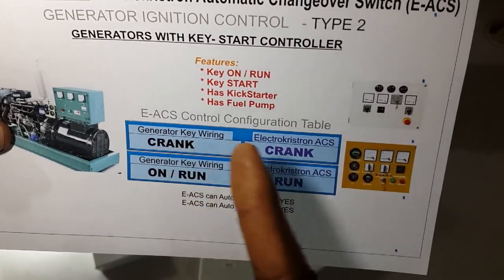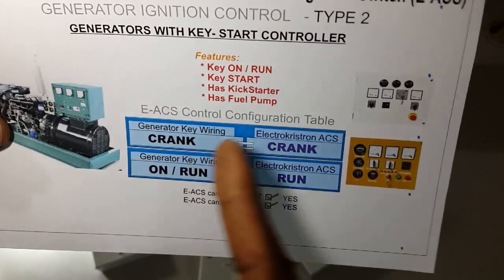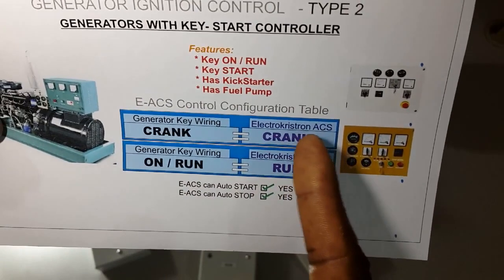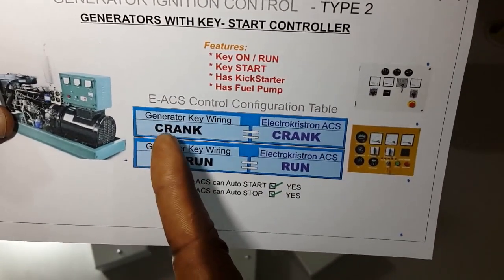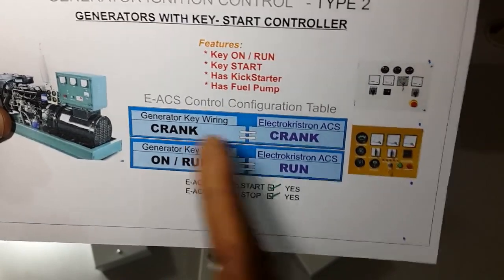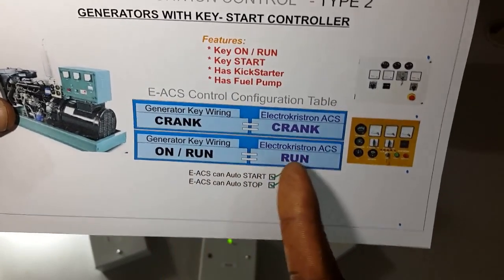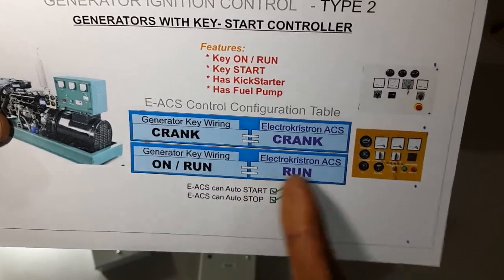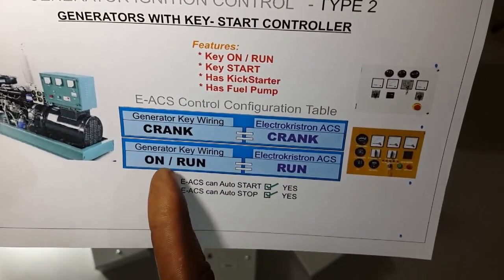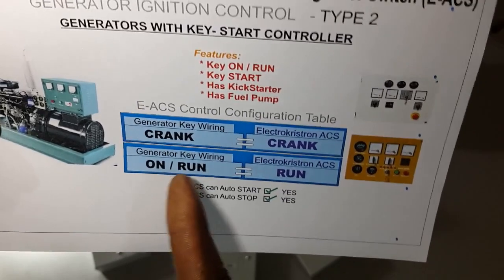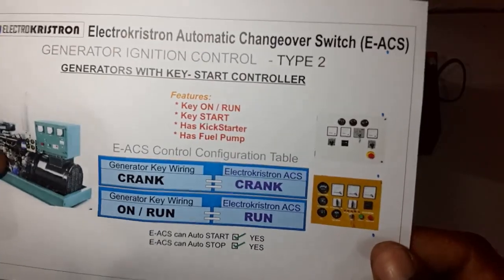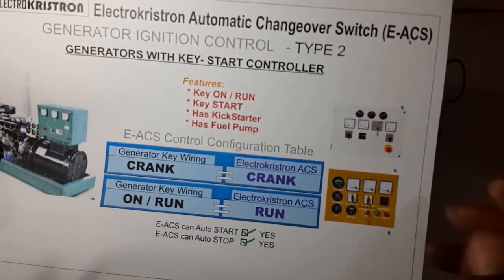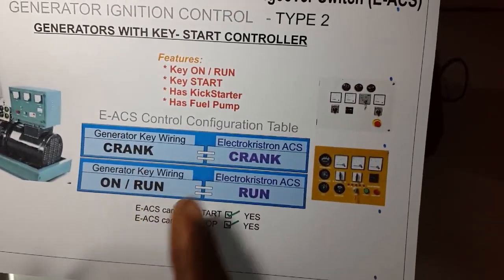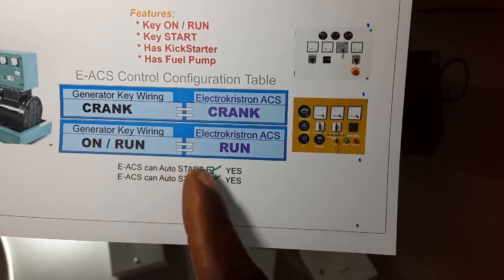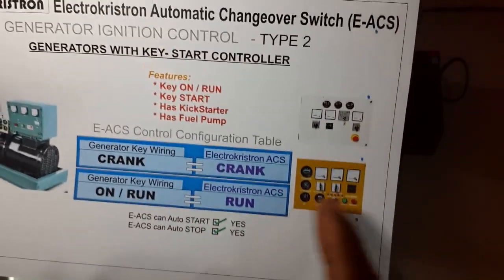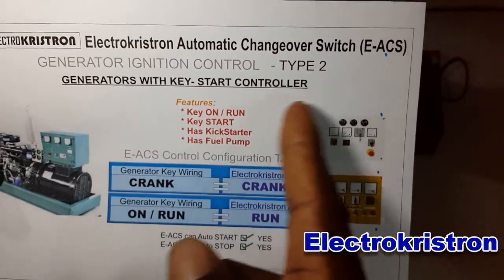You need the crank control on the Electrokristron automatic changeover connected to the crank wiring of the ignition key. You also need the run command from the Electrokristron changeover switch to be connected to the on or run key wiring on the generator. This type of generator, the automatic changeover can start them, and it can also stop them automatically. That is for the type 2.